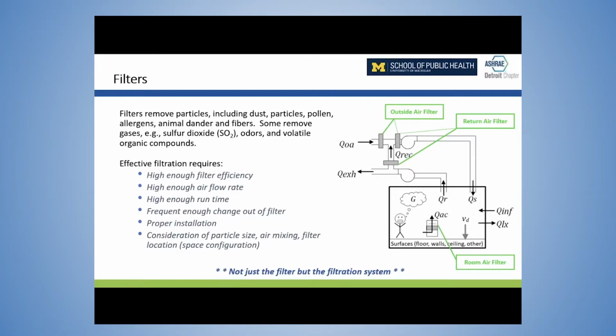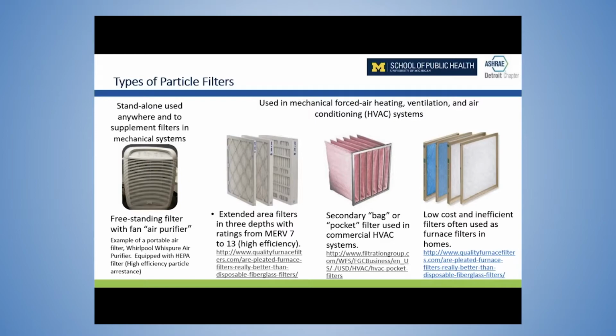So I'm sure most of you are familiar with the different types of filters that are available. On the left, we have a standalone portable air filter. We have pleated extended depth filters, secondary or bag filters. The combination of those extended area and secondary bag filters providing mechanical air filtration is really the preferred approach. On the right, we have some low-cost fiberglass filters, rarely seen in schools, although I have seen some that are furnace filters, which basically will collect leaves and some dust, but won't do anything for PM 2.5.